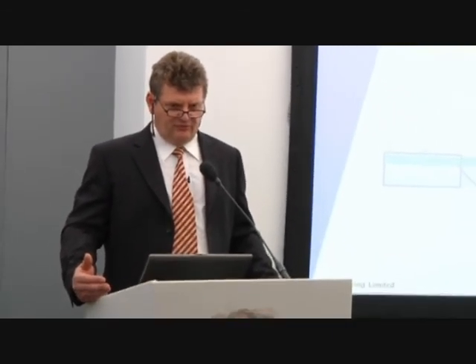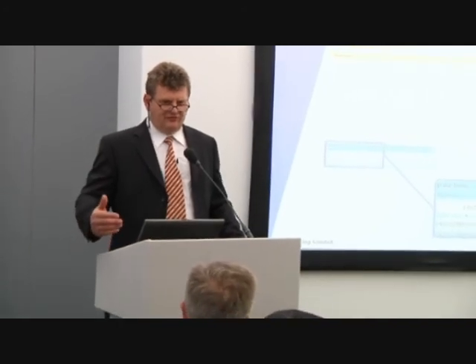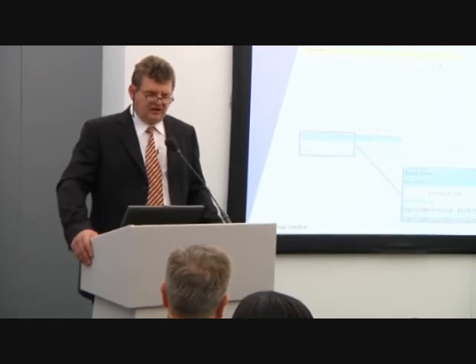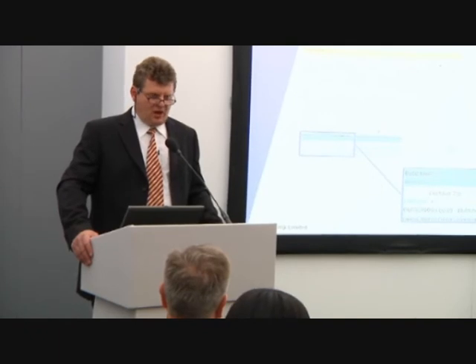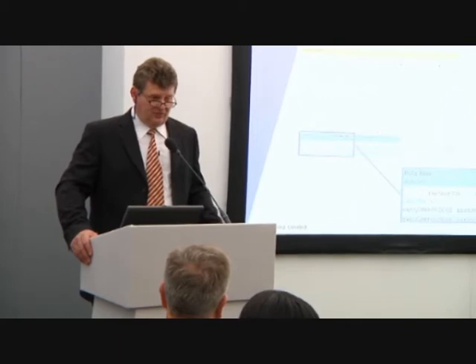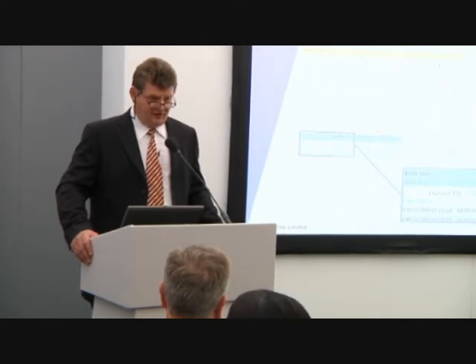For these guys to achieve less than 1.2 is real world-class performance. Google claimed to have the most efficient data centres in the world at about 1.2 to 1.22. You see some very bespoke designs now being put forward, but these are really based on very custom engineered solutions for fixed-size data centres. To take a legacy data centre, retrofit a simple piece of equipment, and achieve this world-class performance is a position they're rightly very proud of — and financially makes a very big difference.